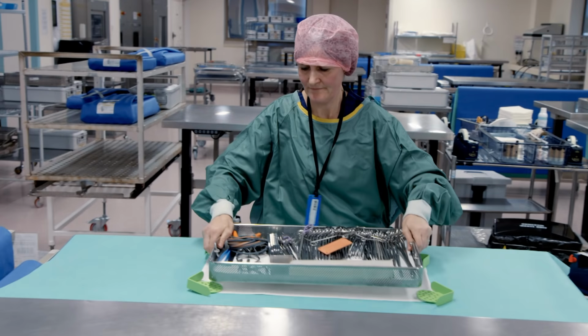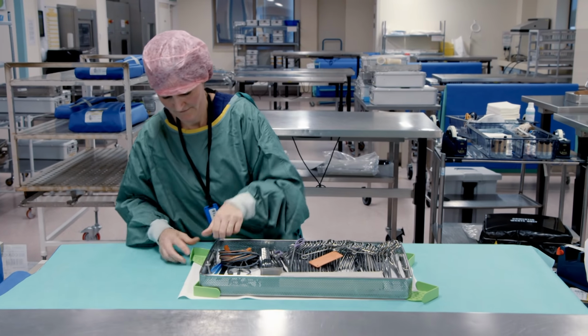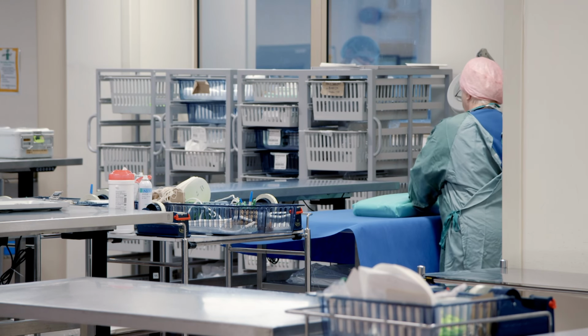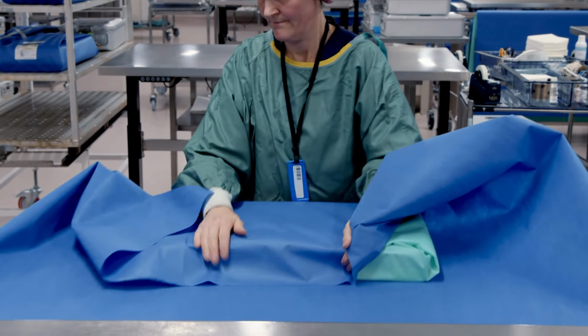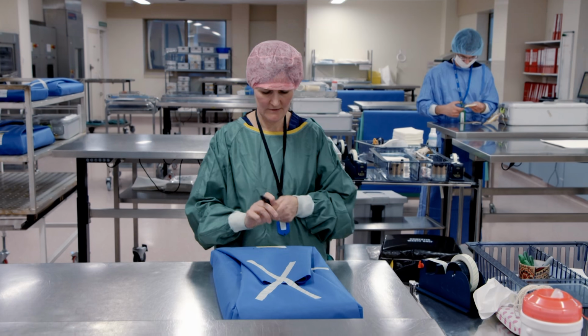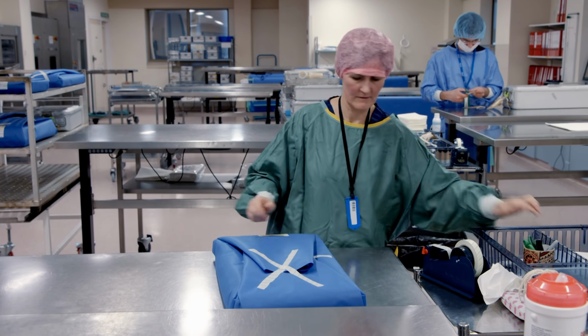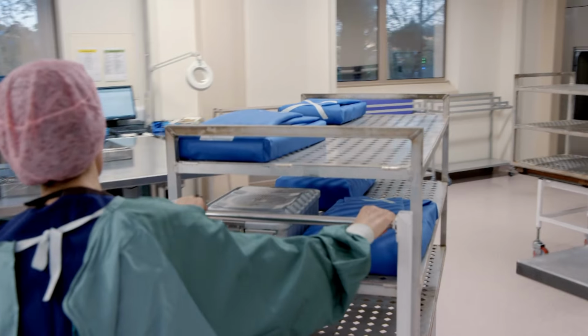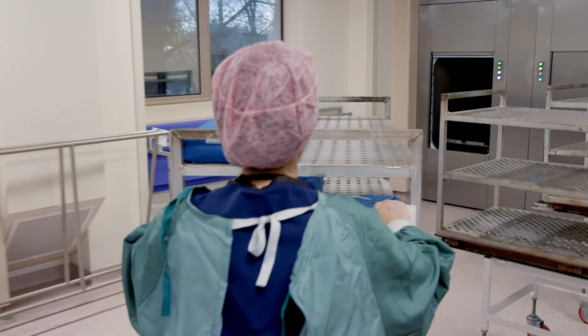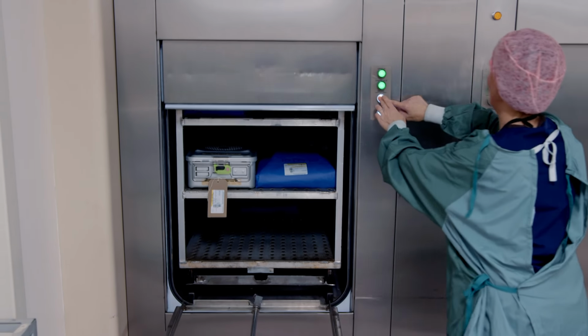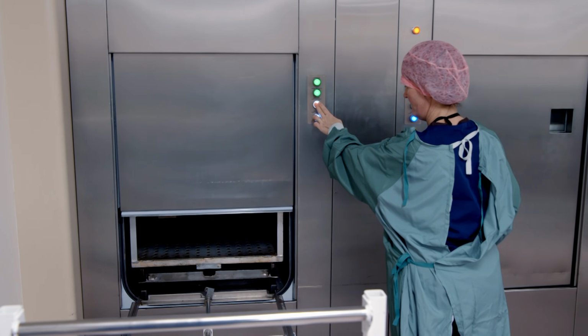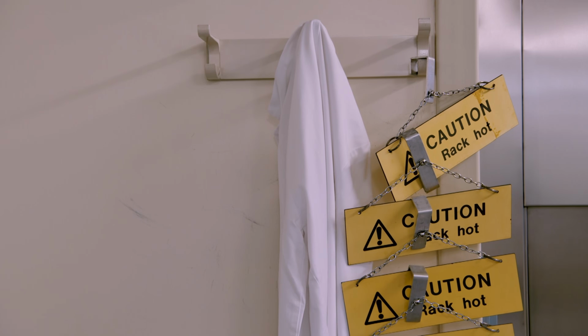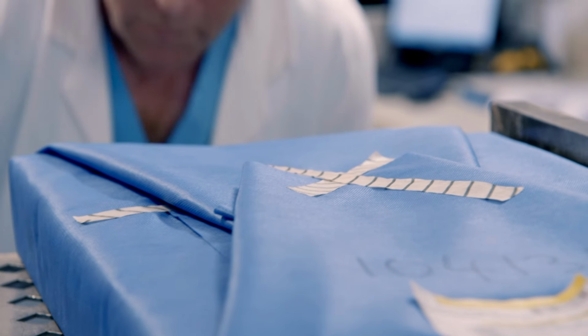Before sterilisation, each set of washed and checked instruments is wrapped. It looks like a simple parcel, but the cloths and the sticky tape are designed with hidden qualities. Once steam sterilised under pressure at 135 degrees C for 3.5 minutes, the stripes on the tape have changed from green to black.